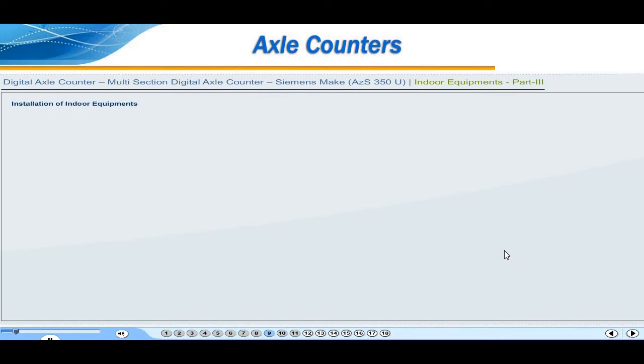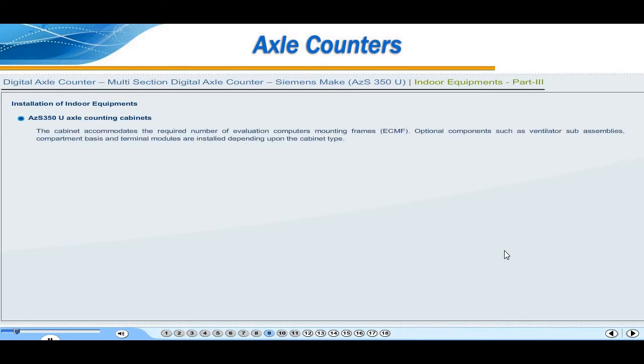Installation of indoor equipment. AZS350U axle counting cabinets. The cabinet accommodates the required number of evaluation computers and mounting frames, that is ECMF. Optional components such as ventilator, sub-assemblies, compartment bases and terminal modules are installed depending upon the cabinet type. Its cabinet has the following variants: S25552J605U1, that is U1 cabinet; S25552J605U2, that is U2 cabinet. It has mounting frame with plug-in circuit boards.